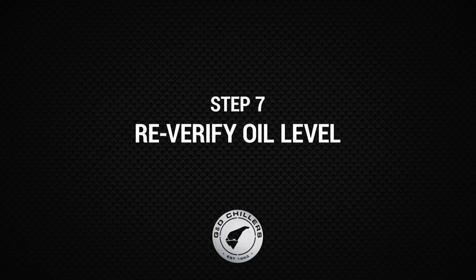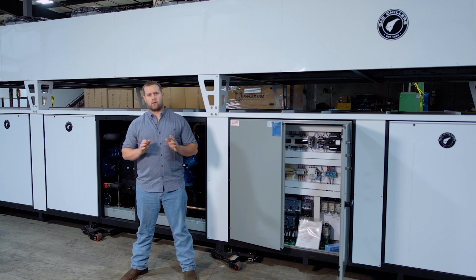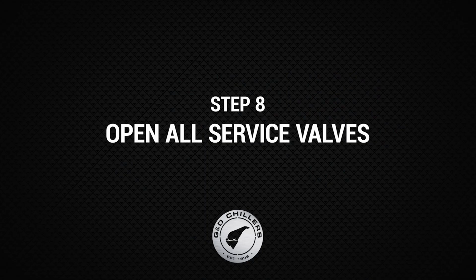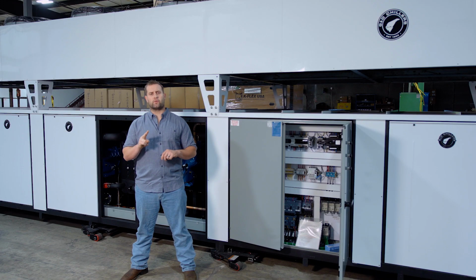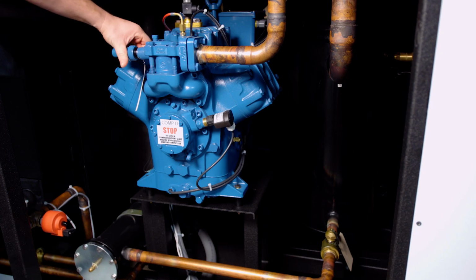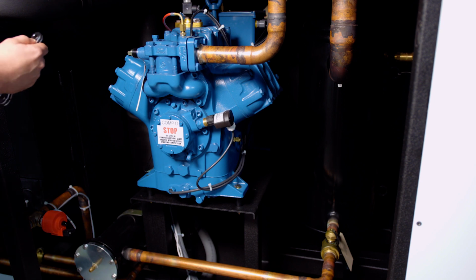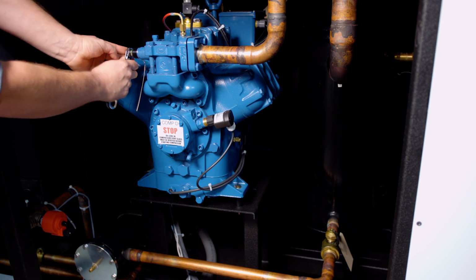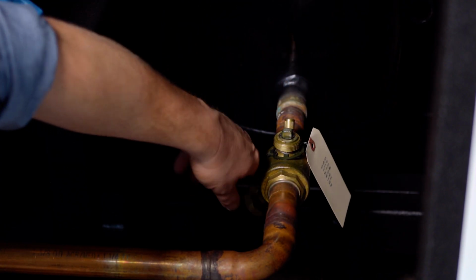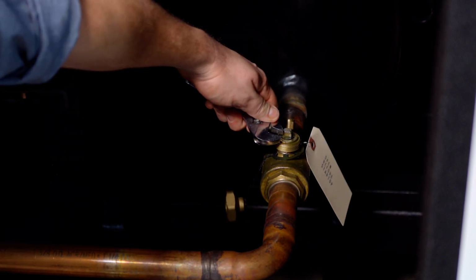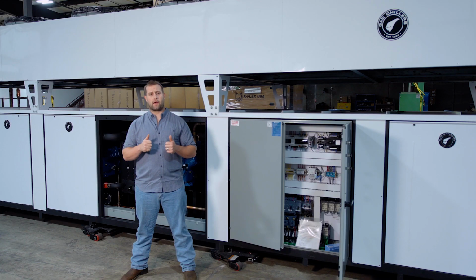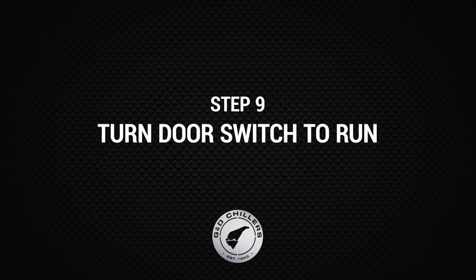Once you're done flushing and filling with glycol, re-verify oil levels in the compressors, and open up all your service valves. You're going to have 2 valves on the compressor, on your suction and discharge, that are going to be tagged. You're also going to have a refrigerant ball valve on your liquid line that you have to open. Once all those valves are open and you've verified the oil levels, you're good to start the chiller.